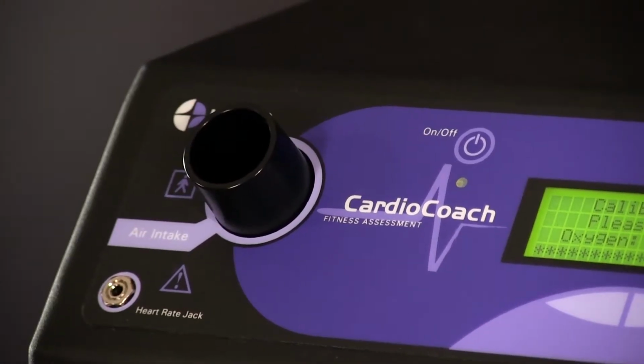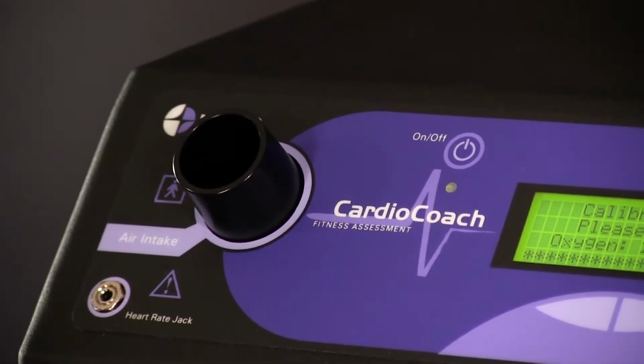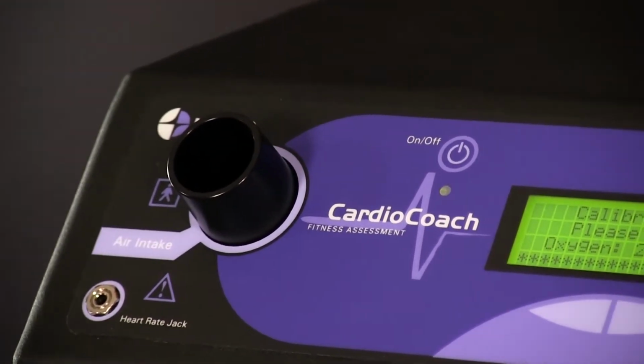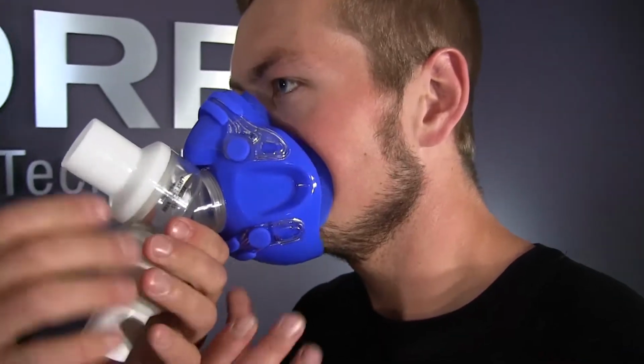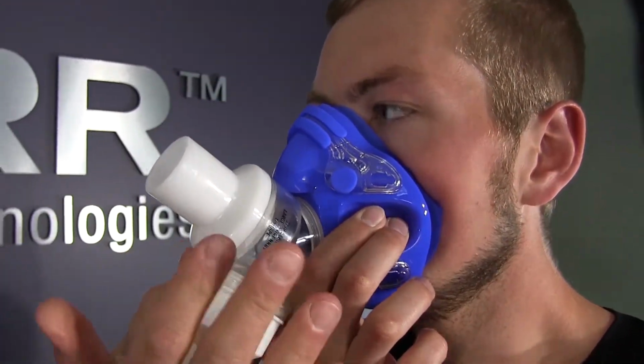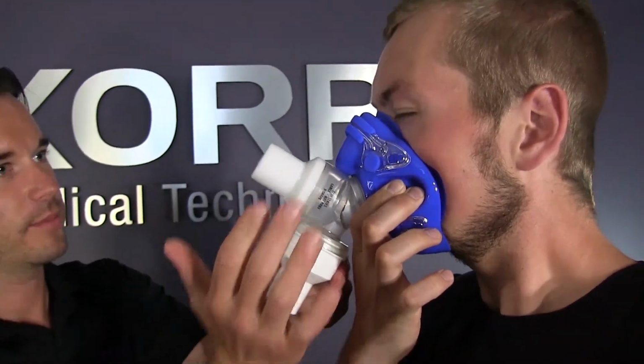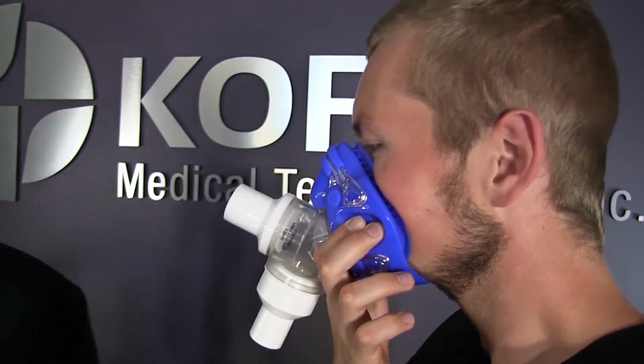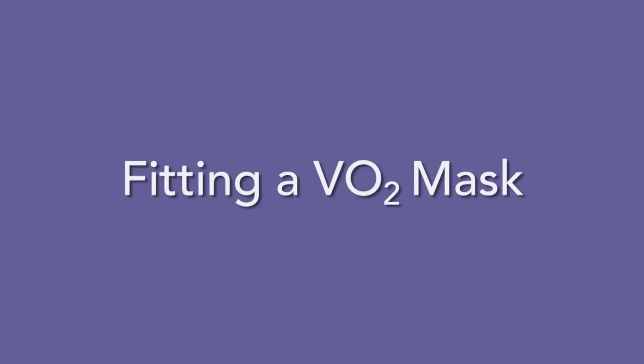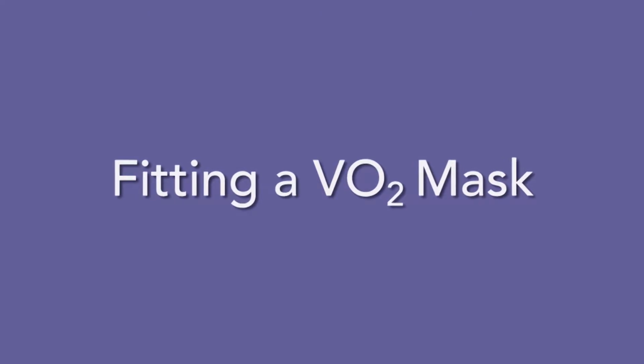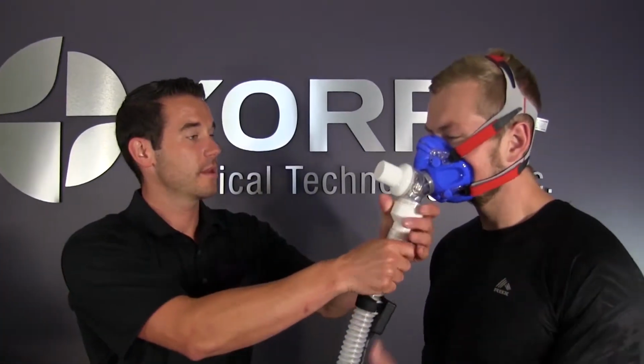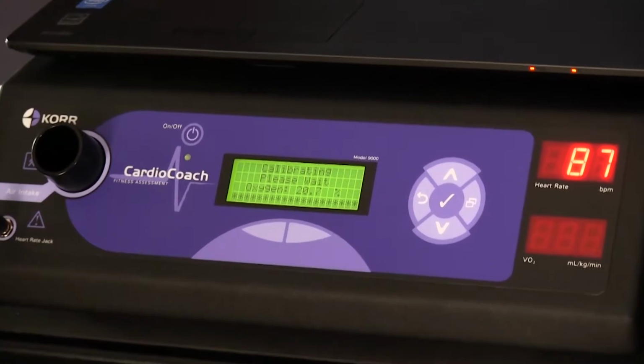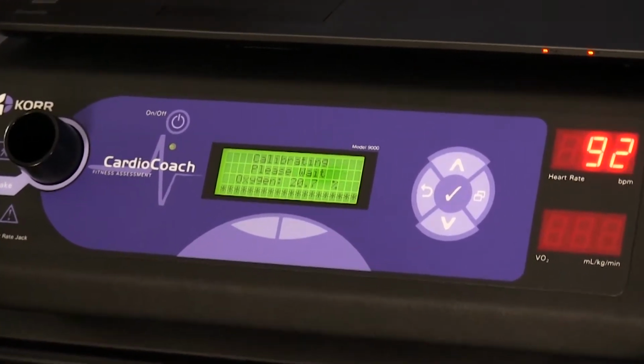Make sure that nothing is blocking the air intake valve and that the tube is not connected. Calibration usually lasts 1 to 2 minutes. During calibration, you can fit the client with the VO2 mask, so they can be ready to start the graded exercise test as soon as the calibration cycle is complete. In order to get accurate results, it is important to make sure your client's VO2 mask is properly fitted before you test. You can use the machine's calibration time to fit and secure your client's face mask.